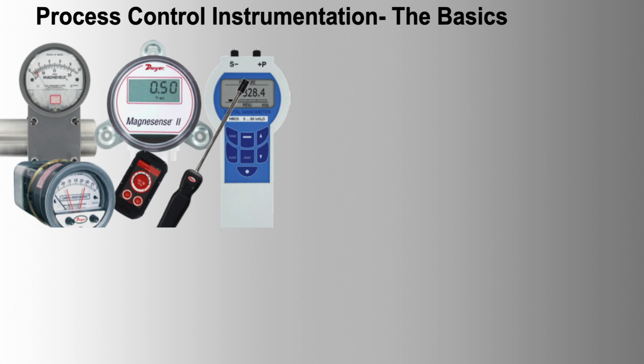Pressure instruments. 1. Range and accuracy. Ensure the pressure instruments can measure the full range of pressures expected in the system with the required accuracy. 2. Material compatibility. Instruments must be made from materials that are compatible with the process fluids to prevent corrosion and ensure longevity. 3. Temperature effects. Consider the effects of temperature changes on the accuracy and reliability of pressure measurements. 4. Response time. The instruments should have a fast response time to accurately capture pressure fluctuations.